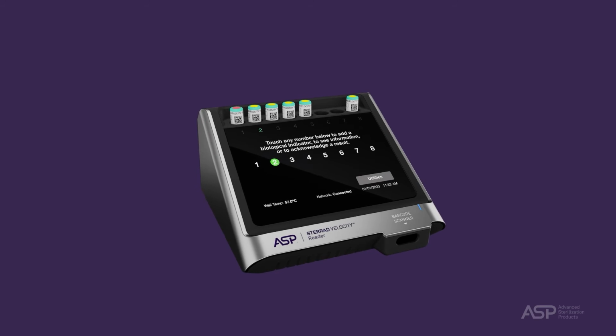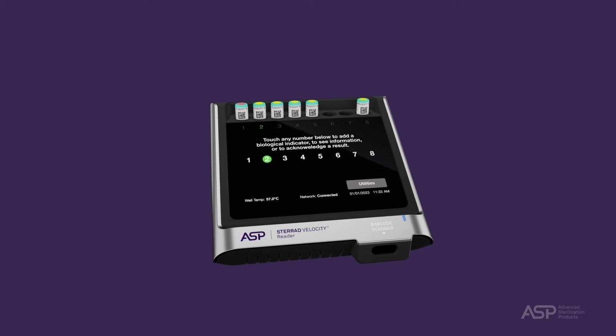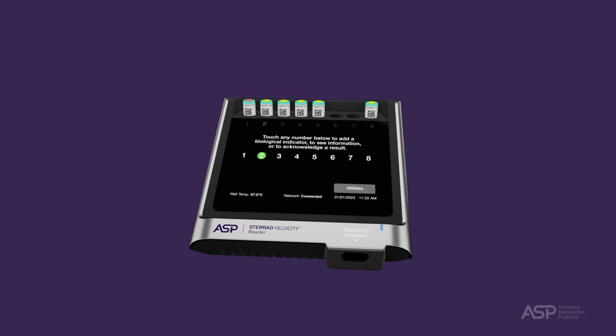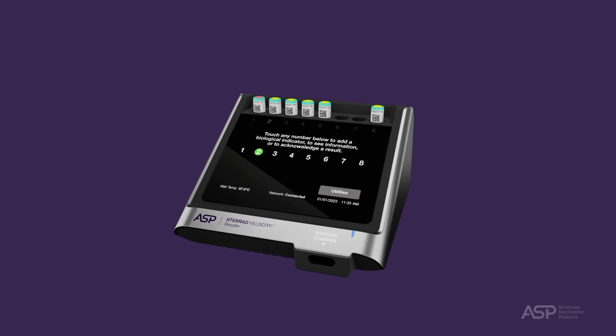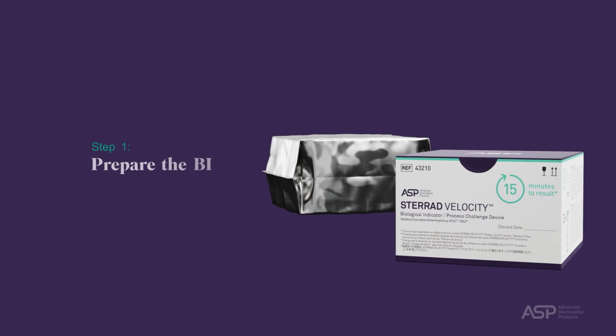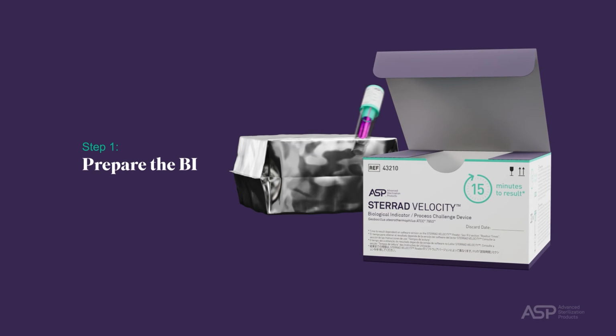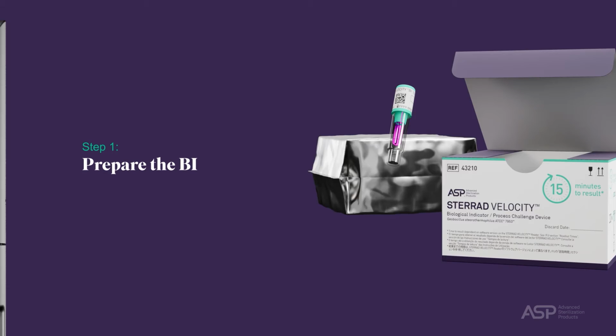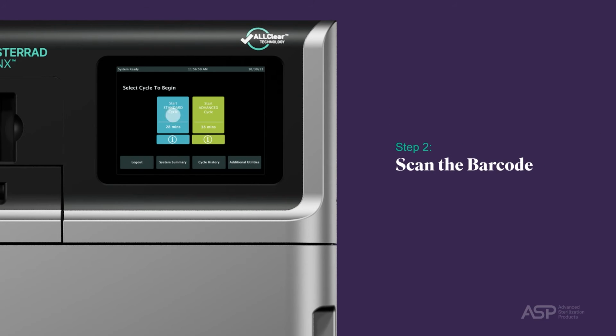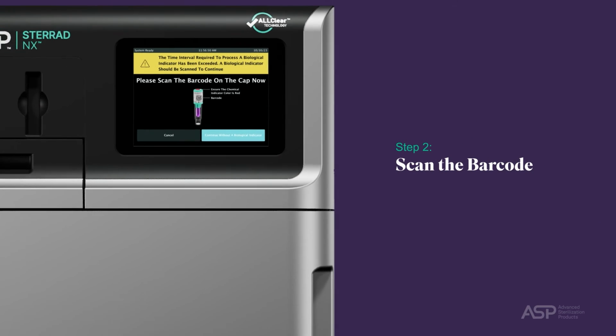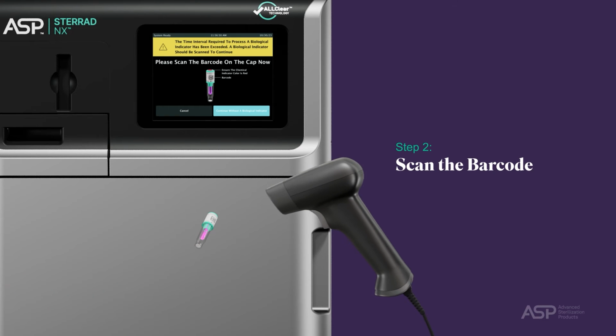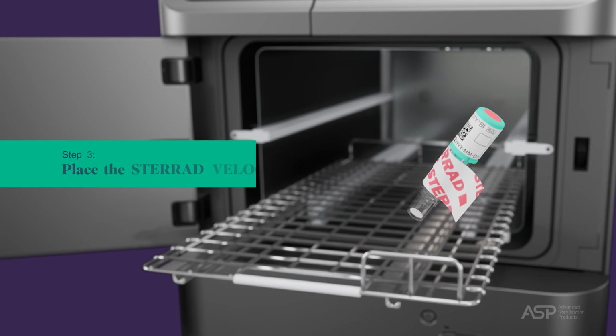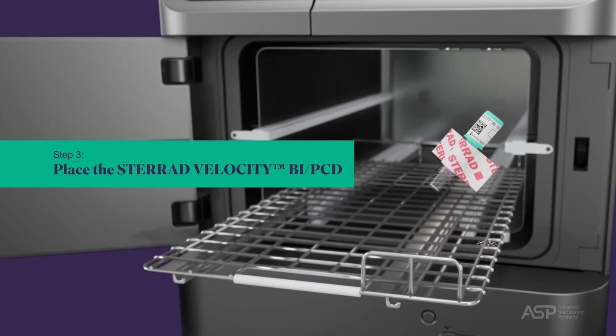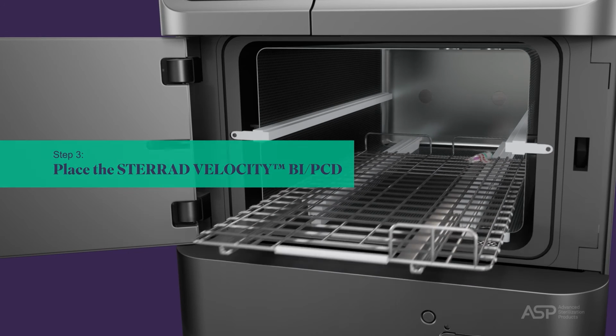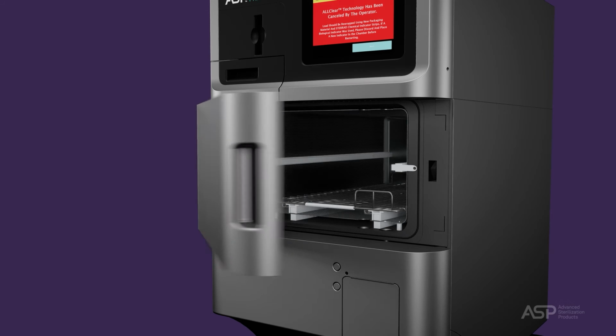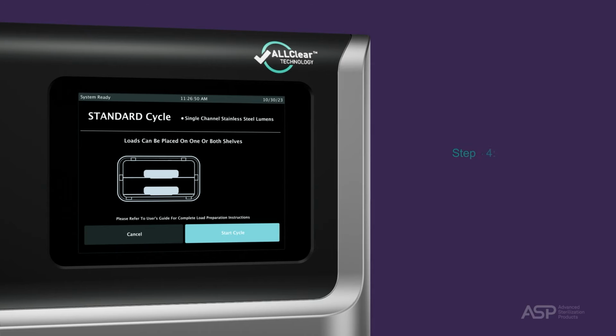If you are using the STERRAD Velocity Biological Indicator (BI)/Process Challenge Device (PCD) and STERRAD Velocity Reader, the following steps should be followed. Step 1. Prepare the BI as specified in the instructions for use. Step 2. After selecting the desired cycle, follow the on-screen instructions to scan the barcode with a sterilizer scanner. Step 3. Place the STERRAD Velocity BI/PCD in the back of the STERRAD NX Sterilizer chamber as specified in the instructions for use.